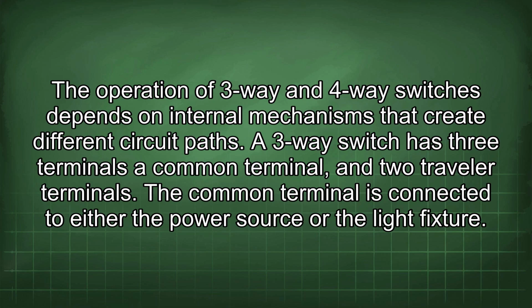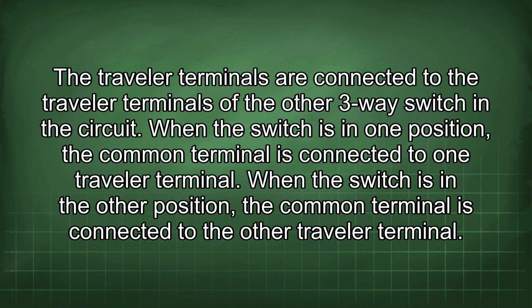The operation of 3-way and 4-way switches depends on internal mechanisms that create different circuit paths. A 3-way switch has 3 terminals: a common terminal and 2 traveler terminals. The common terminal is connected to either the power source or the light fixture. The traveler terminals are connected to the traveler terminals of the other 3-way switch in the circuit. When the switch is in one position, the common terminal is connected to one traveler terminal. When the switch is in the other position, the common terminal is connected to the other traveler terminal.